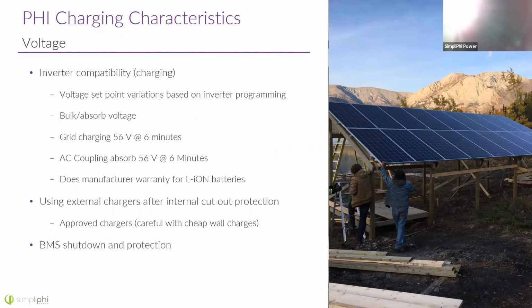Okay, so knowing this, let's talk about the inverter capabilities or compatibilities. One of the most important things, if you're asking yourself whether or not you can use a lithium battery with old equipment, is to ask: is it possible to set the appropriate charge settings into that charge controller? So can we get the appropriate set points? One of the set points is voltage. We want to make sure that we get that absorbed voltage right there at 56 volts. We also want to make sure that we can control the charging rate, right? And so that's the constant current process. So we want to have both of those settings there.